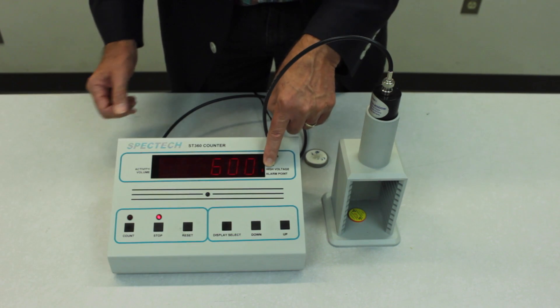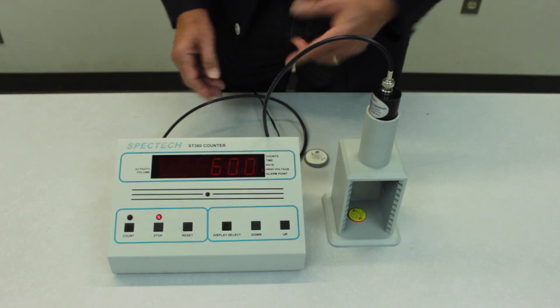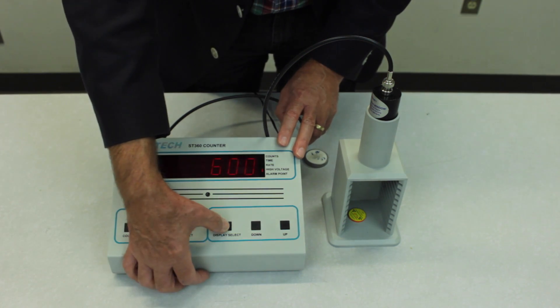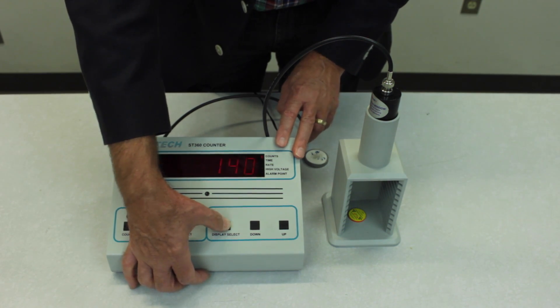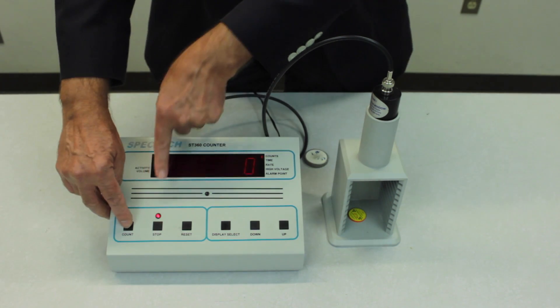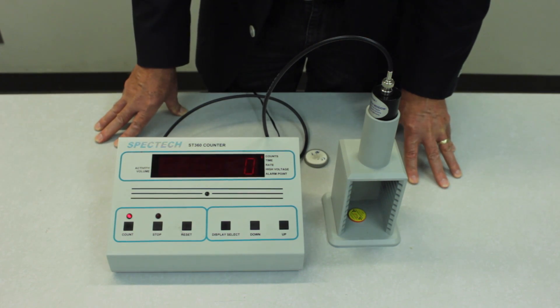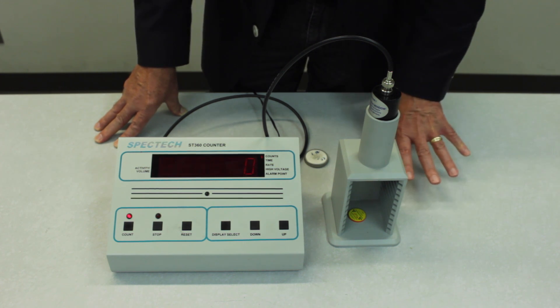Actually there. Six hundred may be below the threshold. So let's find out if that's the case. We'll go back to the count function and reset this to zero and press the count. And it's just sitting there not counting anything. So six hundred volts is probably below the threshold.